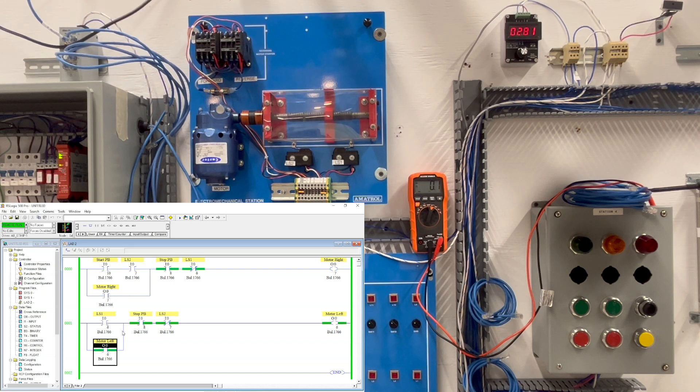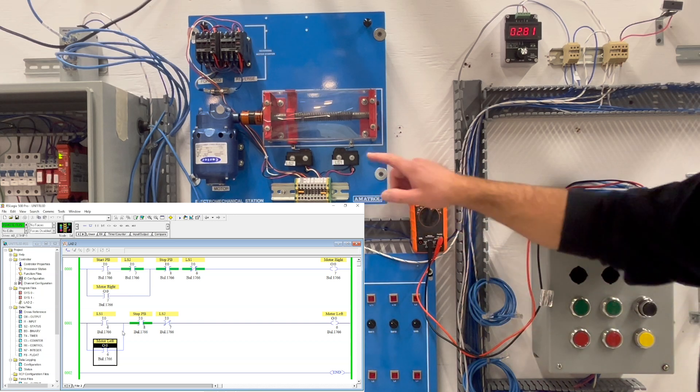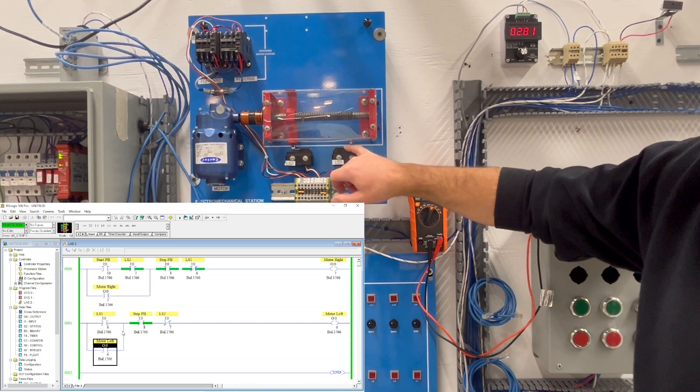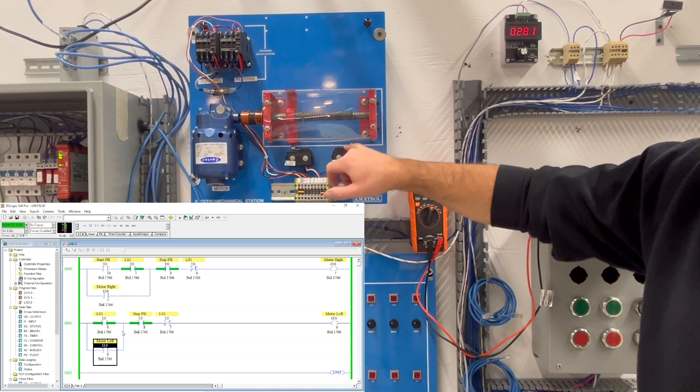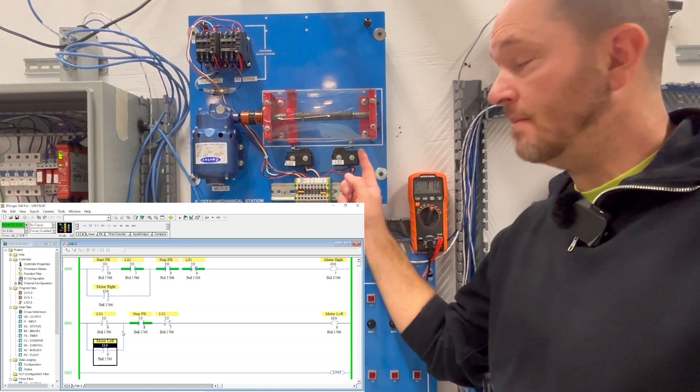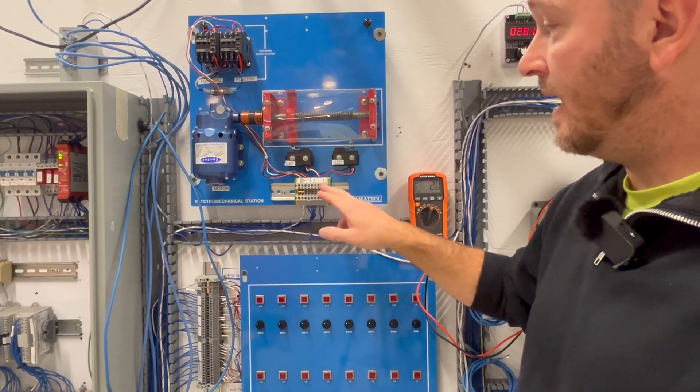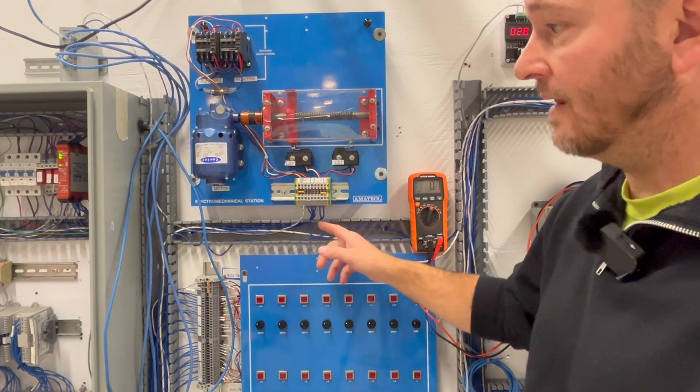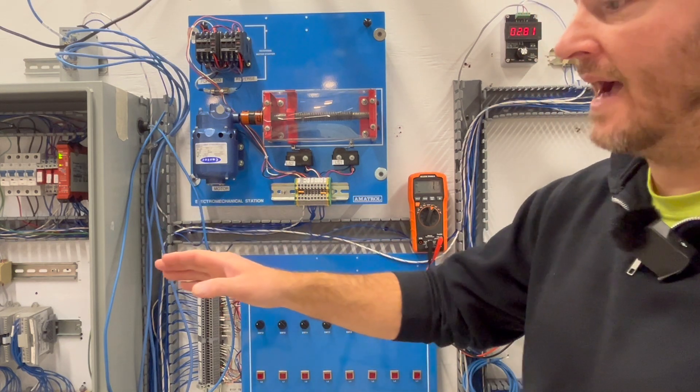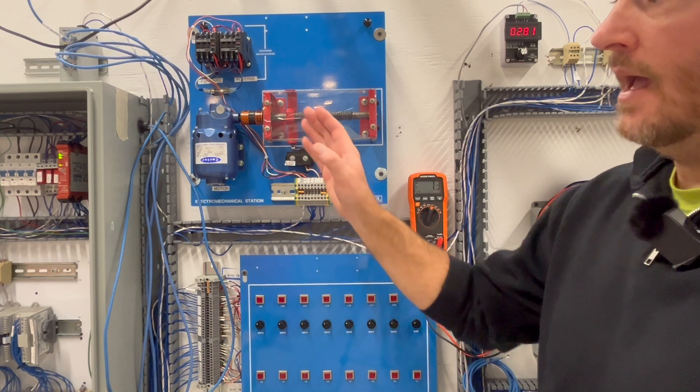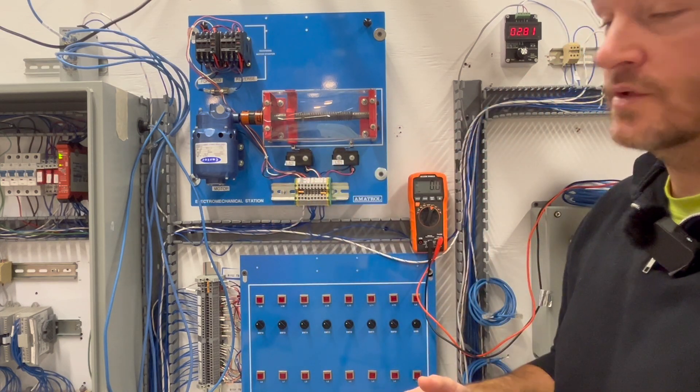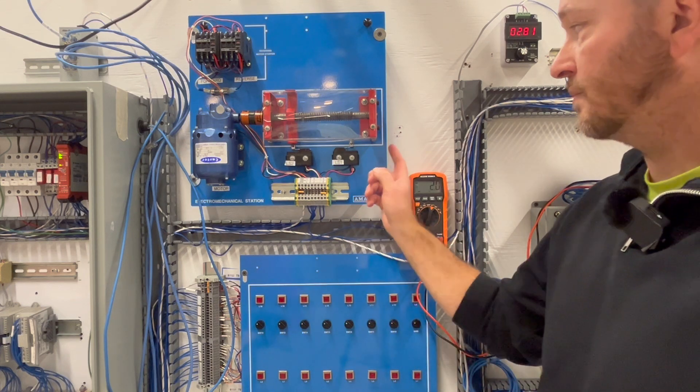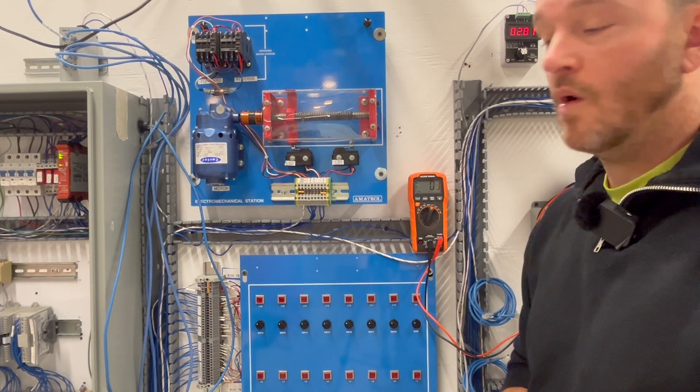And there we go, now I know it's operating and I can go ahead and stop this. And now if I'm confident I can come in here and you can see that I am getting, I am reading something right there on the PLC. Now if this hadn't been the problem, let's say I was getting voltage here, I would have had to trace that line all the way back through using my schematic diagram and tracing the wires back all the way to the input to see what was going on. But in this case this is a pretty easy one, my LS1 was bad.